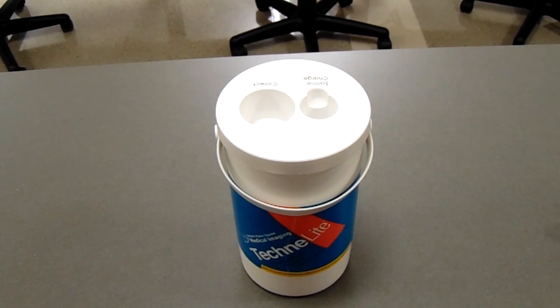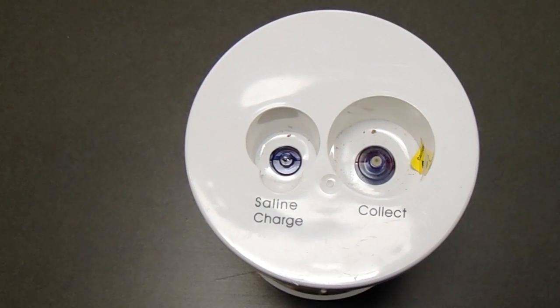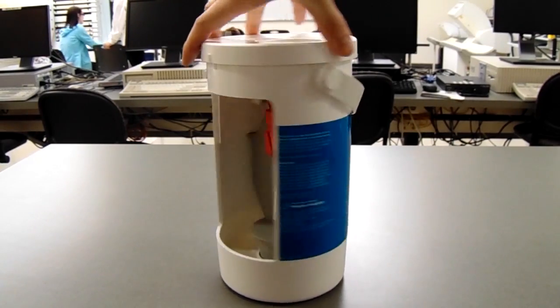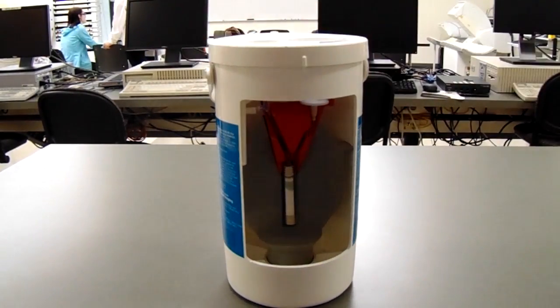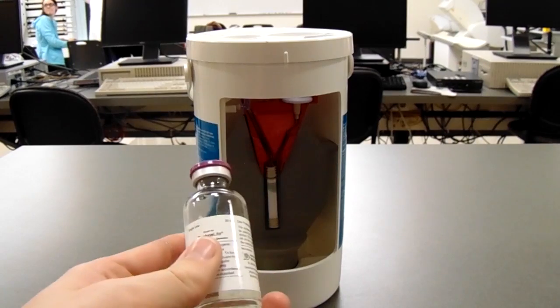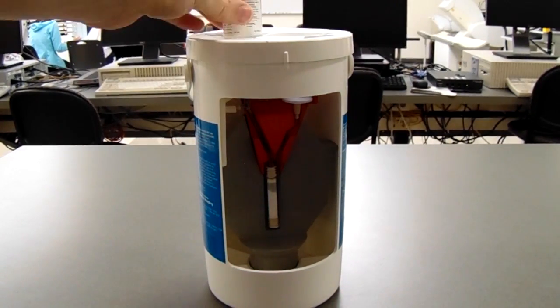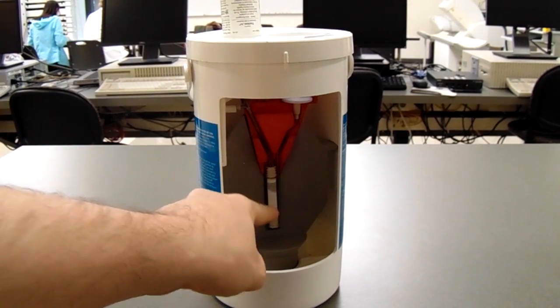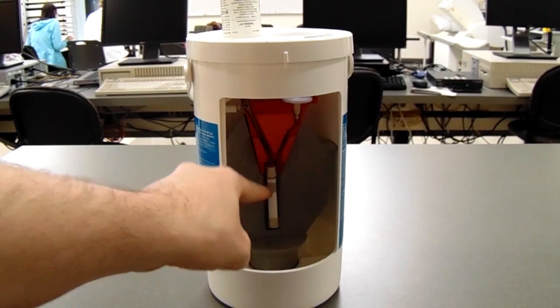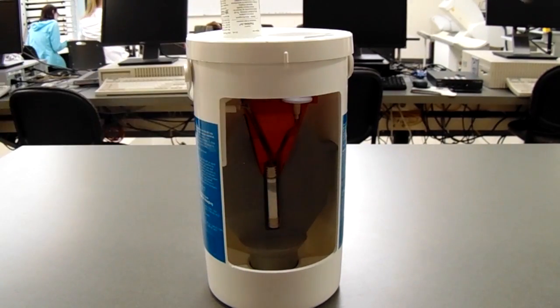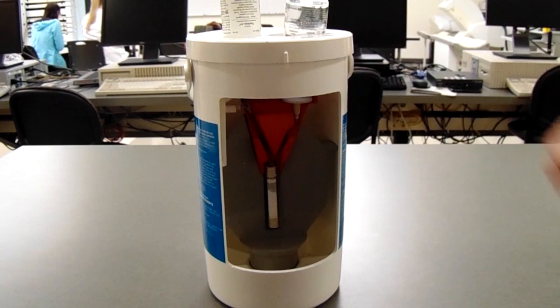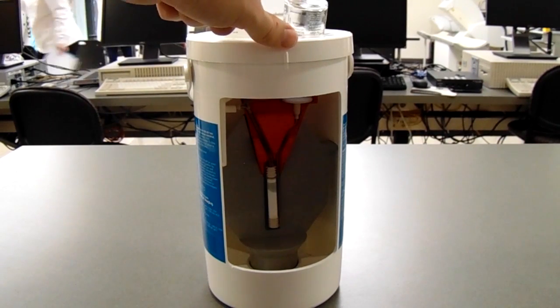Now, this is your Mollytech generator. It's got a saline side and a collect vial side. The saline charge will have 2 needles and the collect vial will have 1 needle. Basically, the way it works is that the saline charge goes into the top of the generator and it creates a vacuum, and the saline will go down, pick up any technetium that's decayed off the molybdenum, and then it will be sucked into the eluate vial due to the vacuum.